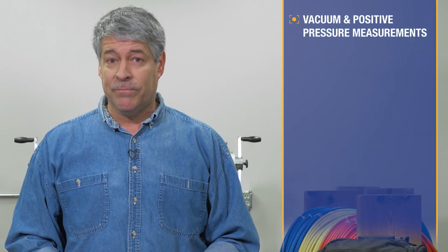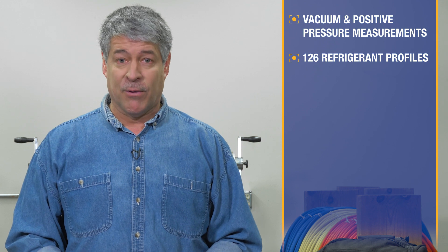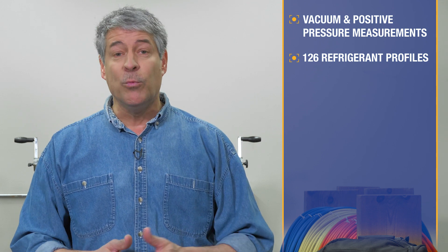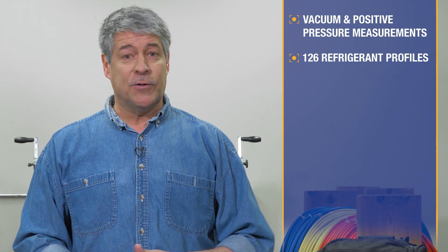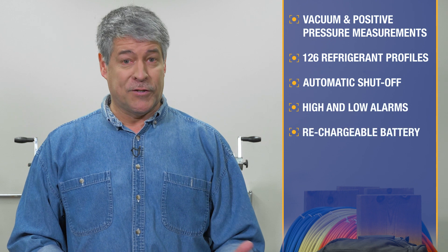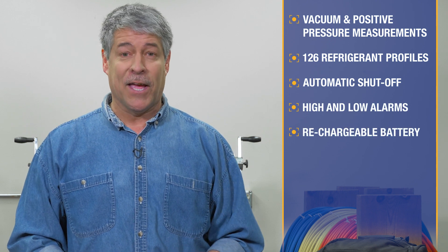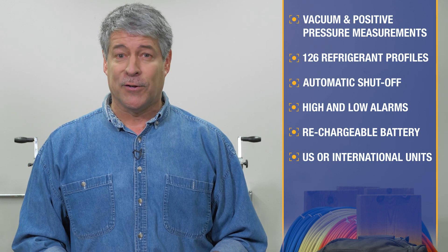The units display rate of change for both vacuum and positive pressure measurements. 126 refrigerant profiles are stored in the instrument, including new blends not currently on the REFPROP database. Other features include automatic shutoff, high and low alarms, a rechargeable battery with battery life indicator, and the ability to display either U.S. or international units.